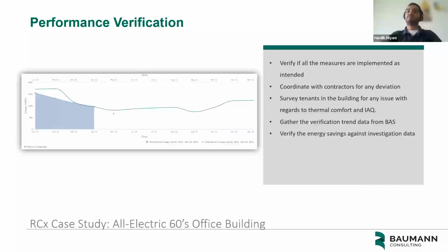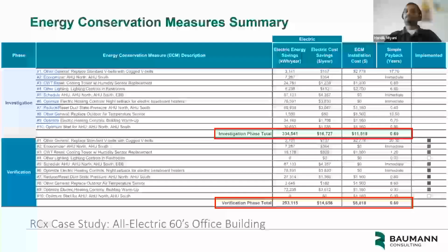There were certainly a few deviations that we saw during the implementation phase, one of them being the optimum start-stop sequence that we recommended. We did try multiple iterations to ensure it was working properly. But since the building was designed in such a way, it was a bit difficult for the optimum start-stop sequence to get implemented properly in this building. So that was a measure that we did not pursue at the end.